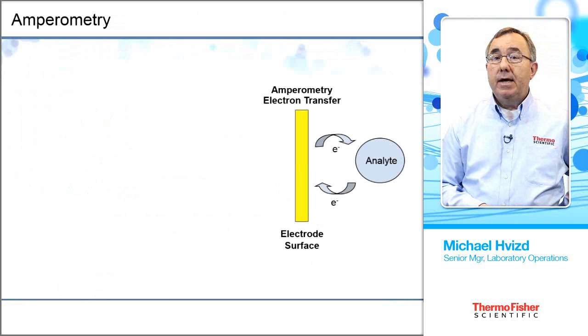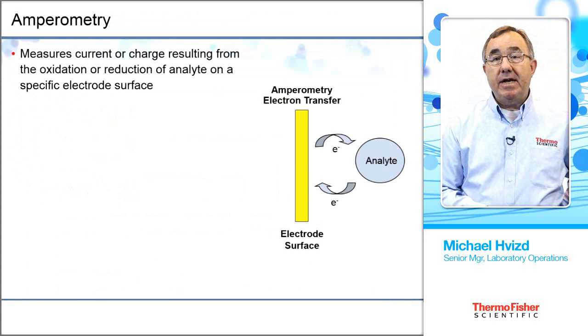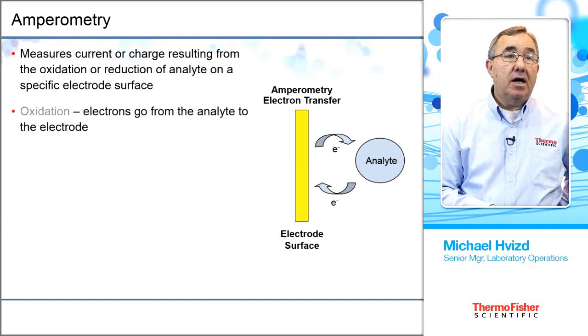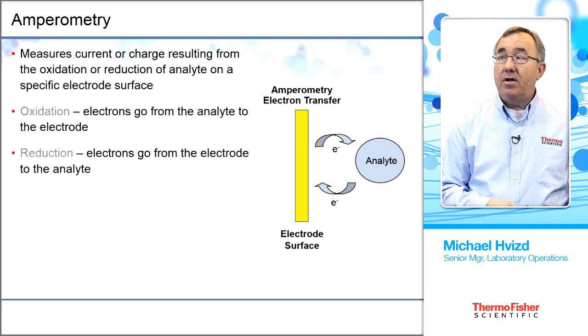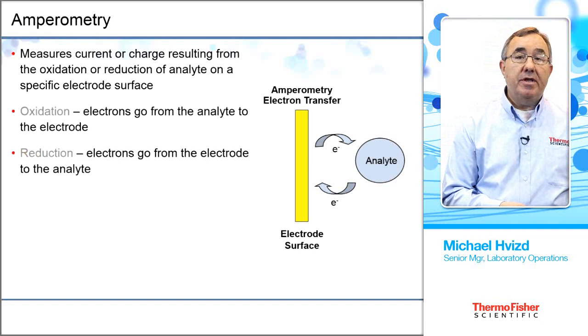Next, let's look at the detection technique. Amperometry is a technique whereby we measure the current or charge resulting from the oxidation or reduction of the analyte on a specific electrode surface. When analyzing carbohydrates, we use a gold electrode. During the oxidation reaction, electrons go from the analyte to the electrode. In a reduction reaction, electrons go from the electrode back to the analyte. For essentially every separation we do, the detection scheme is an oxidation reaction — we measure the current based on the oxidation of the carbohydrates on the surface of the gold electrode.